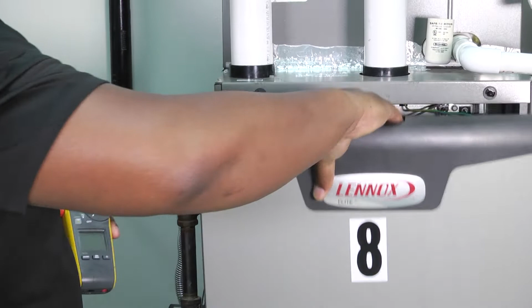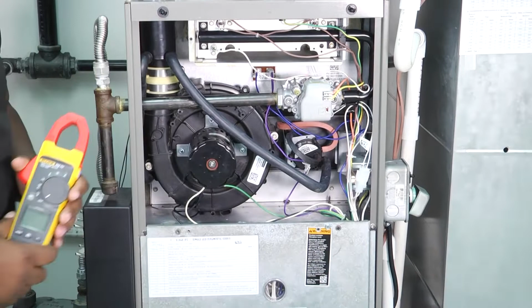You don't want to leave that to someone else. Make sure you turn off the power, and when you get to your unit, use your voltmeter to check at your incoming source of power over at the junction box to make sure you don't have any power floating through there. You might want to grab a meter with a non-contact voltage setting, so you can wave it in there to check for voltage, or take your leads and touch the place where you think the last known source of power is, to make sure things are free and clear.